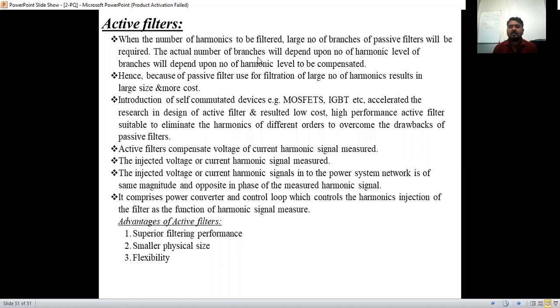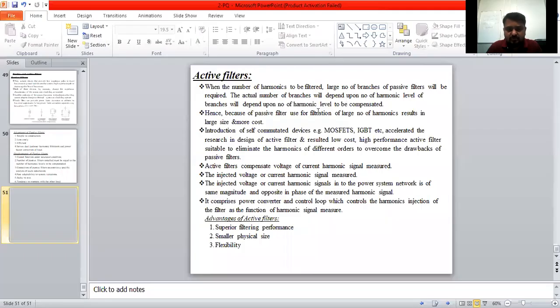So by using that, the number of branches will increase. For that reason, when the number of harmonics to be filtered is large, a large number of branches of passive filter will be required. The actual number of branches will depend upon the level of harmonics to be compensated.